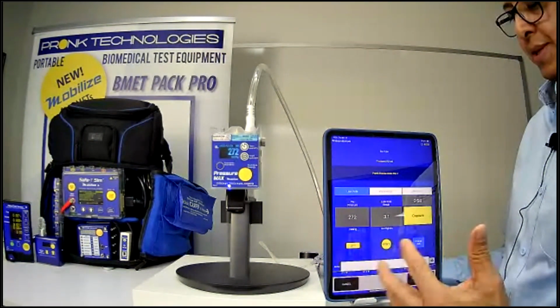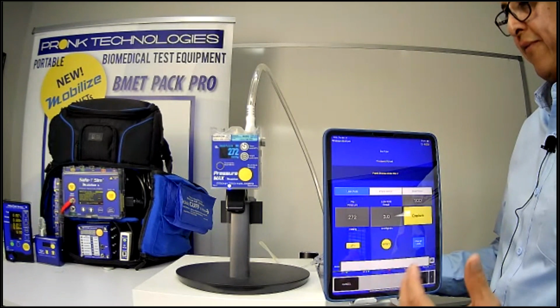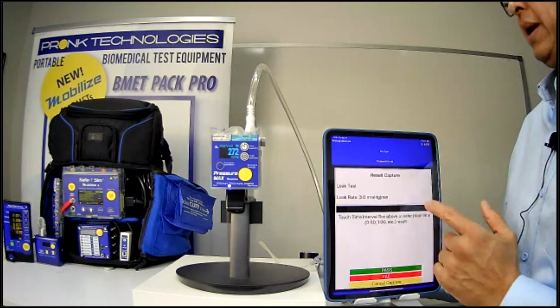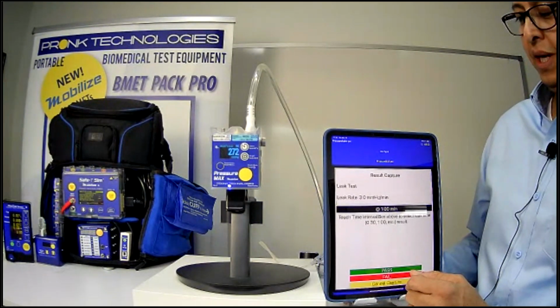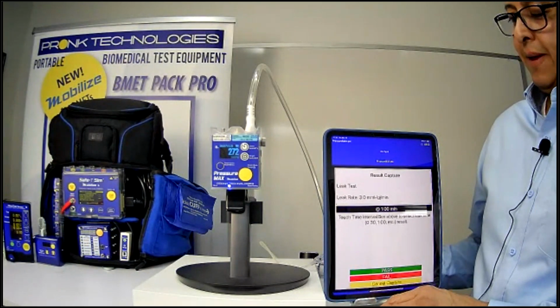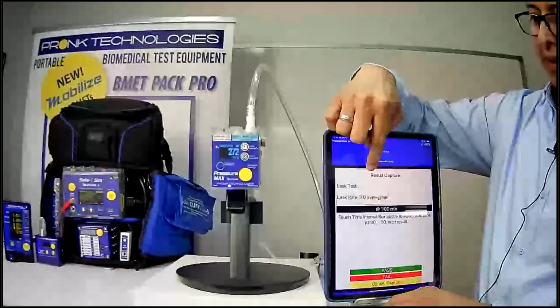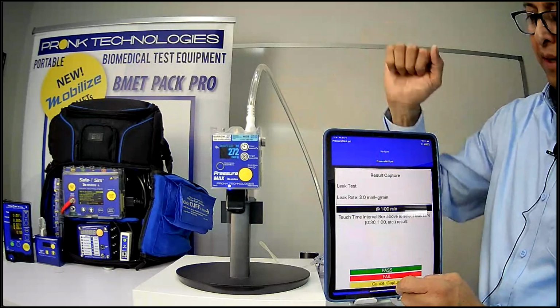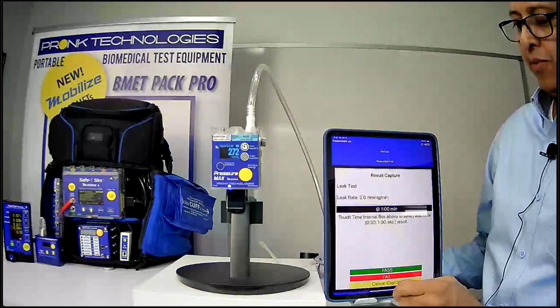Once I'm done with that leak test at whatever interval you need to test to, you can hit the capture button, and you'll see here the leak result, and you're able to see that the leak at 1 minute was 3 millimeters of mercury per minute.